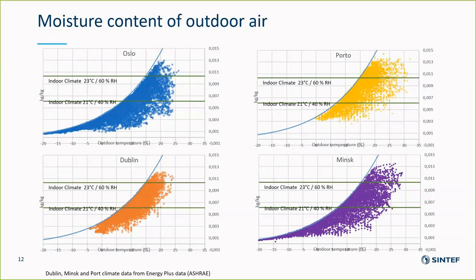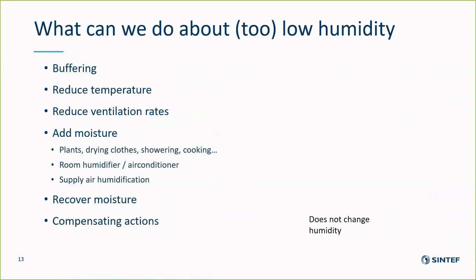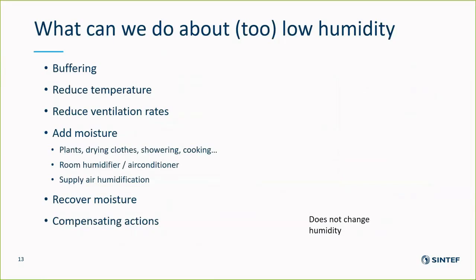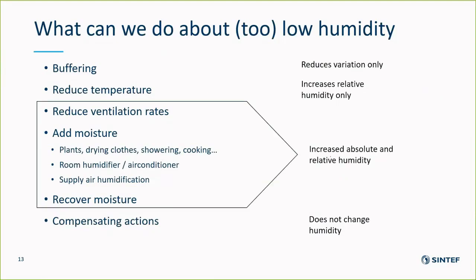So what to do about it? We could do buffering, reduce temperature, reduce ventilation rates and add moisture, try to recover moisture, or just try to compensate for the bad parts. Of course buffering will only reduce the variation, reducing temperature will increase only the relative humidity, while the next steps will increase both absolute and relative humidity.